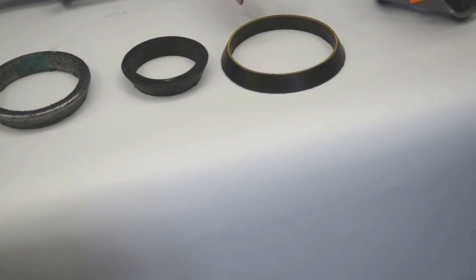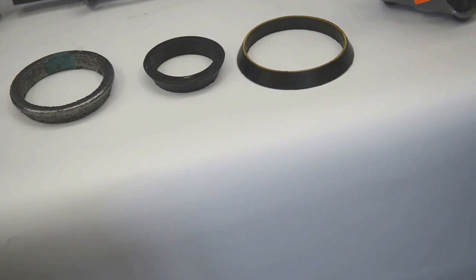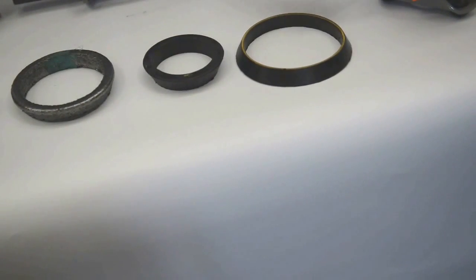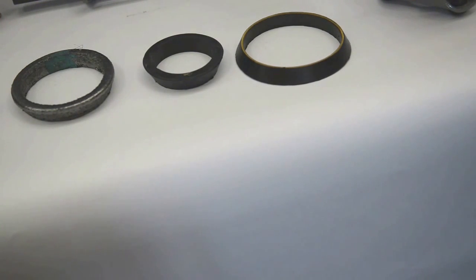That's for natural gas service. It allows metal-to-metal contact throughout. It also protects the rubber from solids that may be in the line. It helps protect the integrity of the rubber gasket.